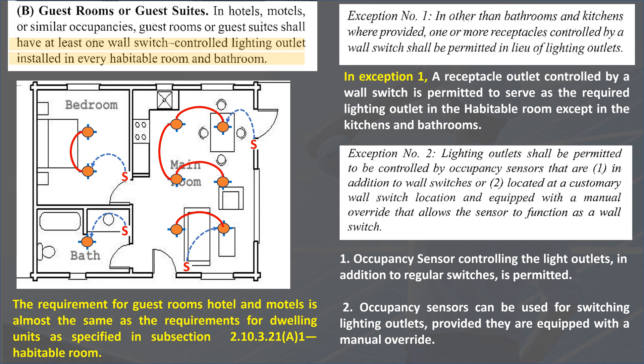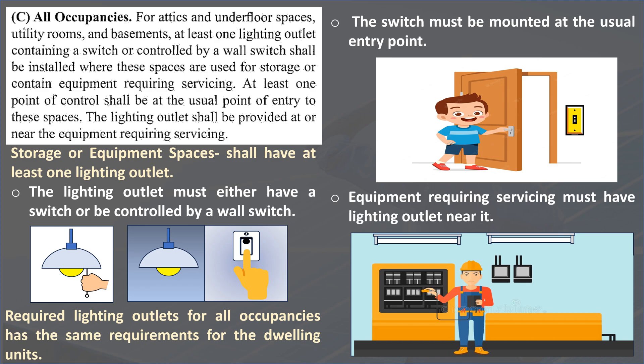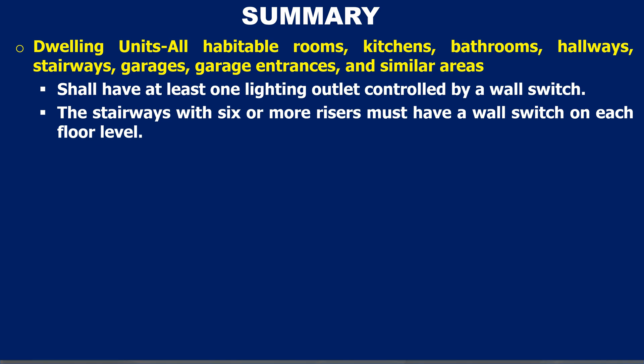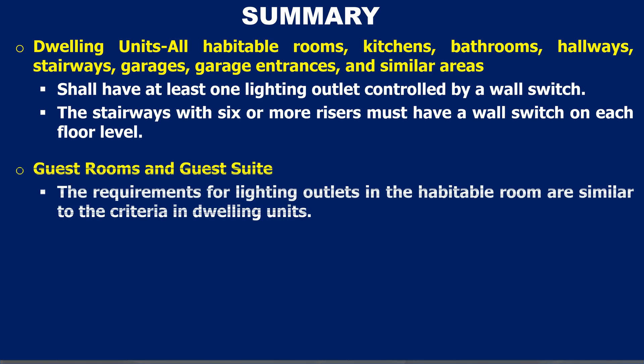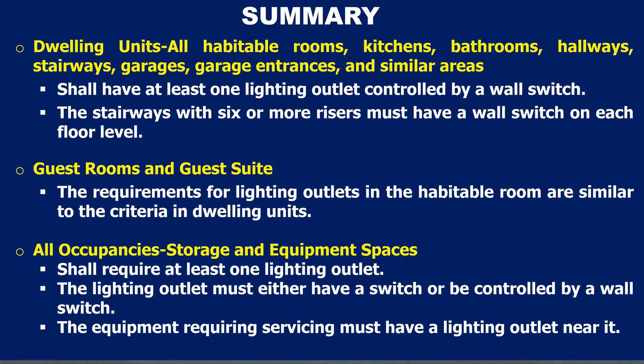Required lighting outlets for all occupancies is similar to subsection 2.10.3.21(a)(3). To summarize: all habitable rooms, kitchens, bathrooms, hallways, stairways, garages, garage entrances, and similar areas in a dwelling unit shall have at least one lighting outlet controlled by a wall switch. Stairways with six or more risers must have a wall switch on each floor level. Storage and equipment spaces for all occupancies shall require at least one lighting outlet, either with a built-in switch or controlled by a wall switch, and equipment requiring servicing must have a lighting outlet near it.